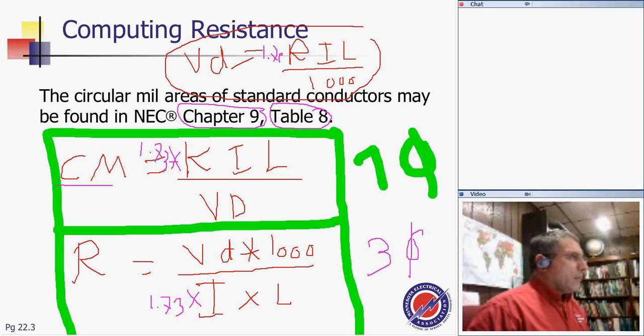Circular mil equals... How many of you guys have used these formulas before? How have you used these formulas? Green check if you have seen them or used them. Anybody? Green check, X, no. Circular mil, don't be embarrassed, no problem. Circular mil equals K times L over the voltage drop, and equals voltage drop times 1,000.